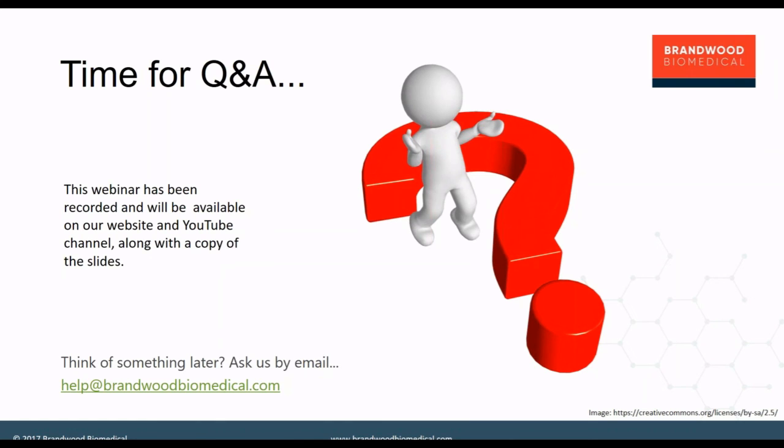There are two aspects there. The first aspect is to put together the dossier as it will be required for the relevant regulator. So if, for example, you send an application in Australia to the TGA, your technical dossier, including the instructions for use, has to be in English. Now, in the context of Europe, your notified body will most likely require the information to be presented in English as well. But at the time of commercialization, you need to have adequate controls to identify what languages are required in the target country, and what languages you have to provide within that technical file.